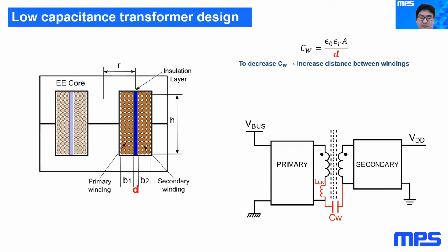So how do we deal with the new requirement for the transformers? The first thing is the interwinding capacitance. The interwinding capacitance can be compared to a parallel plate capacitor. Since the insulation material and area of the coil offer less design freedom, the best way to reduce this capacitance is by separating the two windings, which means increasing the thickness of the insulation layer. As we can see from the equation, the capacitance is inversely proportional to the distance between the two winding coils. So we need to increase that distance to reduce the capacitance.